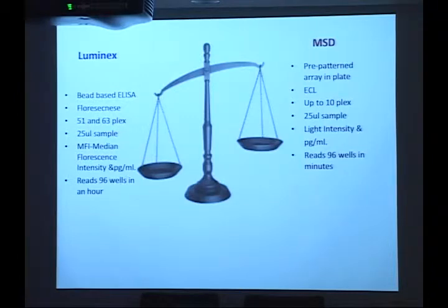So, some comparison for Luminex and MSD. In general, I would say that the advantage of MSD is mainly the fact that you can read a plate in a few minutes. You're limited with the amount of analytes that you can measure for each well, and that has not changed in recent years. But it's very specific and may push better towards the picogram level.